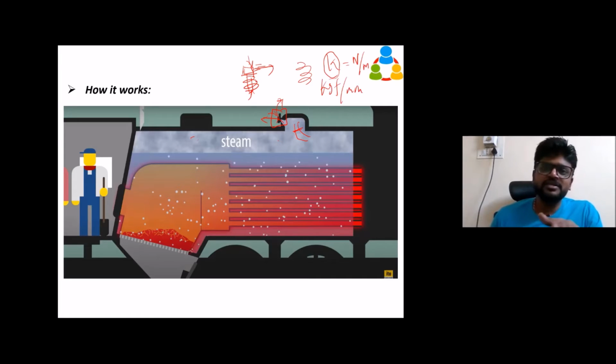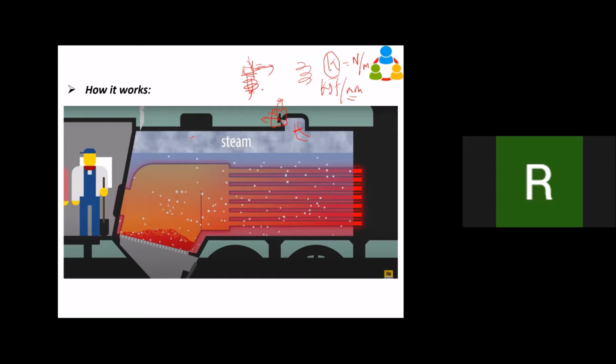From this calculation, they know what value of pressure is safe for your pressure vessel, like a cylindrical vessel. For a safety factor, they'll take some 80% of that value and set the spring, so that if it compresses to that much displacement in mm, it will open. The spring can be bought and set accordingly. And this value also can be varied. The spring settings will be there, so it's not a constant pressure setting. You can vary the pressure settings also.